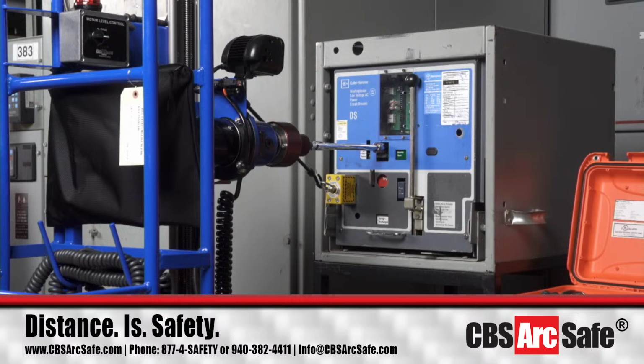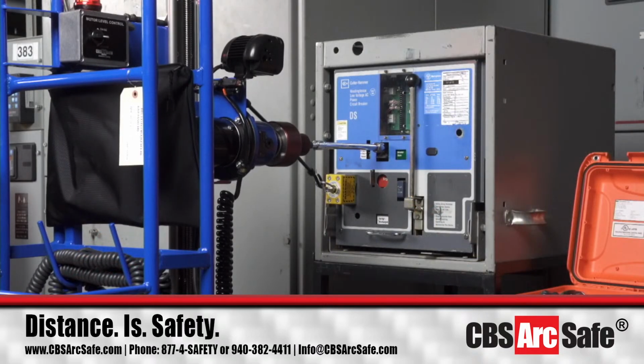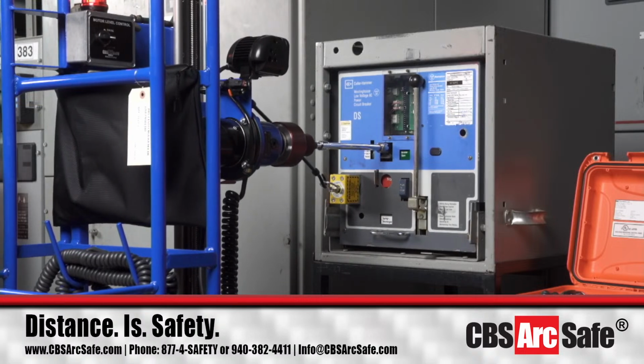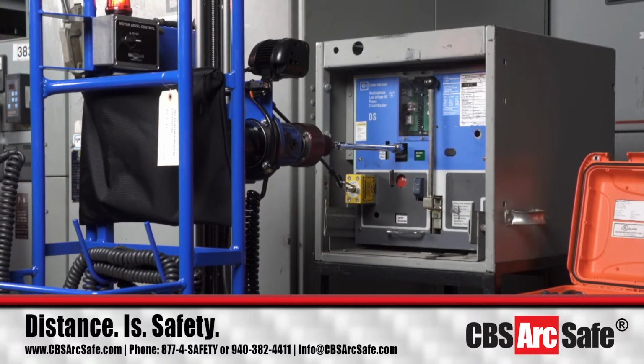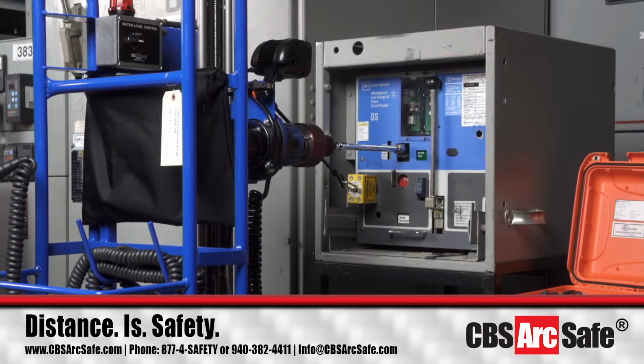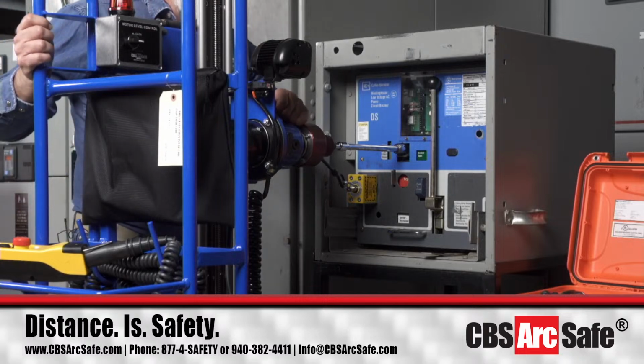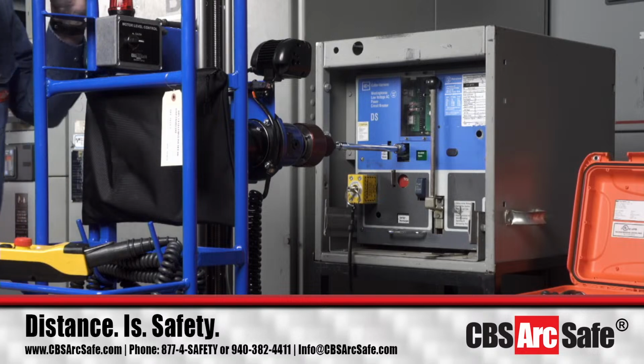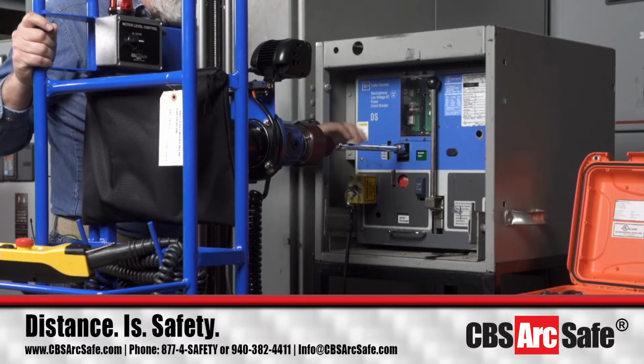And what I'm going to show you is with this one, this is the low speed jog version of the RS1, and after we get it in, I'll jog it out just a little bit with the jog buttons so that we can have it come out just a quarter of a turn and take that tension out of the racking mechanism. Now, let it finish booting here. And there, right there, with that little jog, I was able to move the breaker back just a little bit. And you'll see that when I move the RS1 back, when it's done, the breaker will still have the little mechanism door closed, which is what we want.